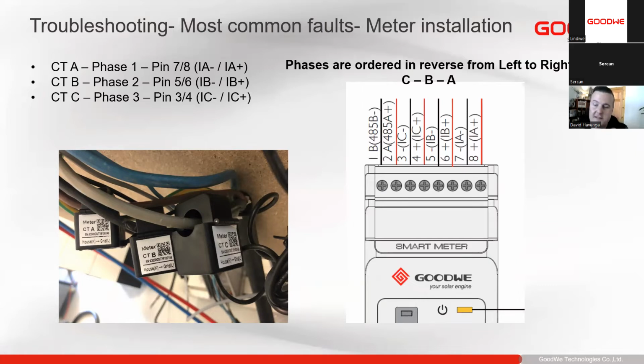I know very often the customer's distribution board is full. We can't put the smart meter into the customer's distribution board, so we put it in a subboard next to that. The easiest way then to run our CTs is to remove these cables, run them through, and then put them back. Please always pay very, very careful attention to installing the CTs back, that A, B, and C are correct. The polarities here are correct, because if you swap the polarity, then the CT direction will be incorrect according to the sticker. So if our polarity is correct here, then our sticker is 100%. So always be sure to, if you remove them, install them back the exact same way.